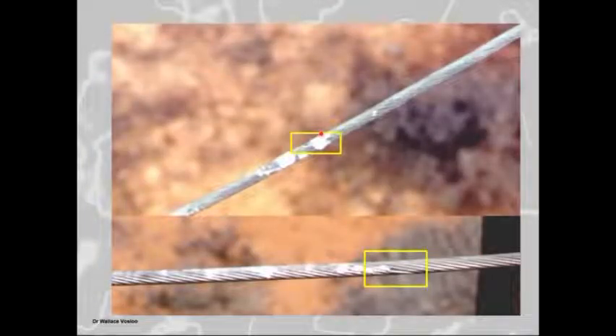Then with a finer inspection with a chopper, we found there's bird excretion on the conductors and flashover marks on the conductors. Ooh, now that is definitely bird excretion with proof of flashover marks at the excretion. And we went further and looked at the earth wires on the tower structures.